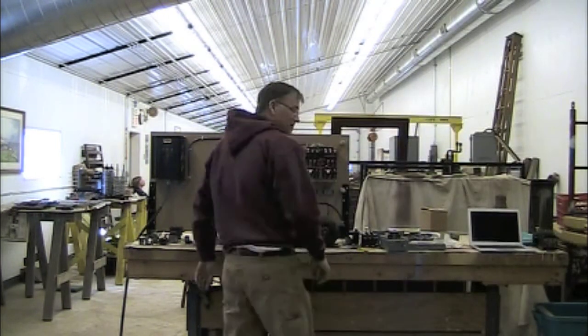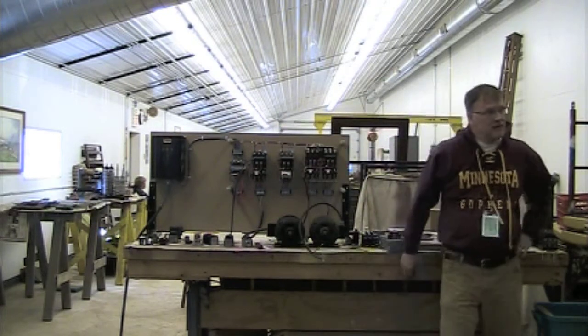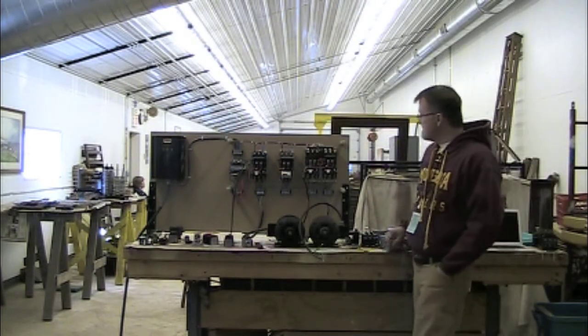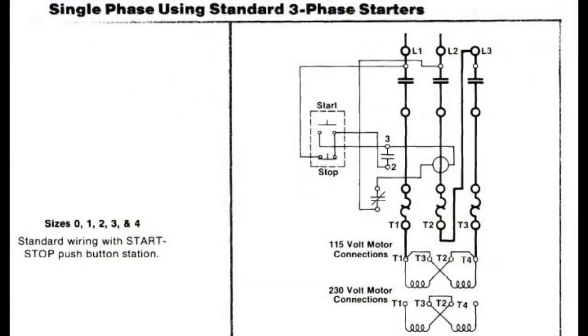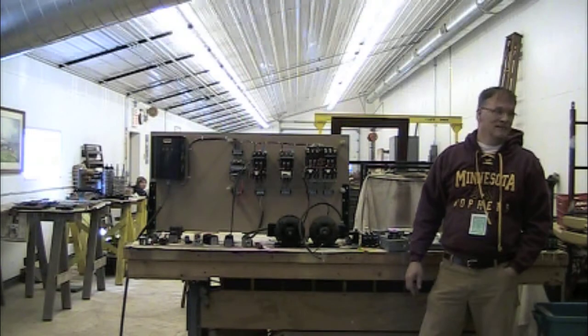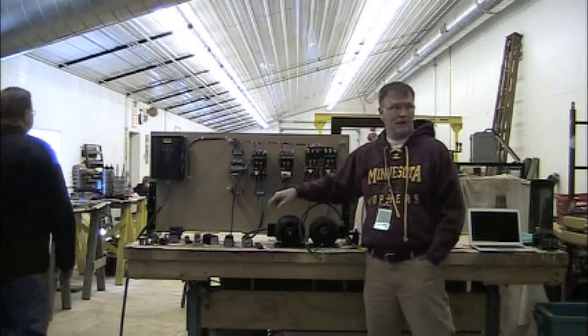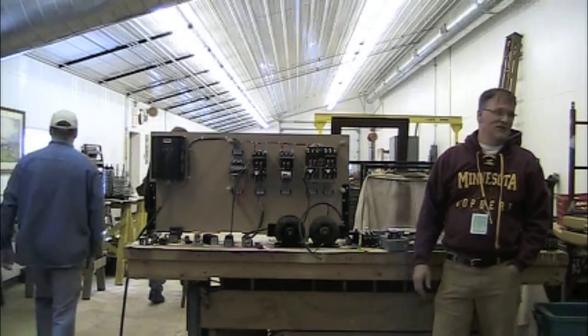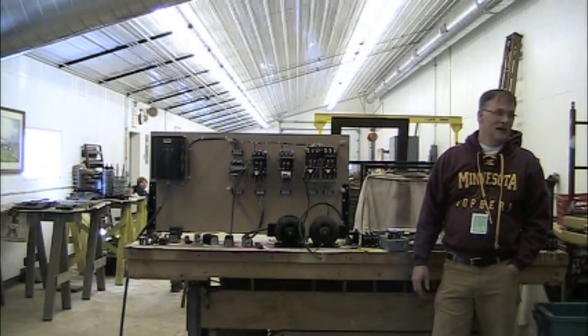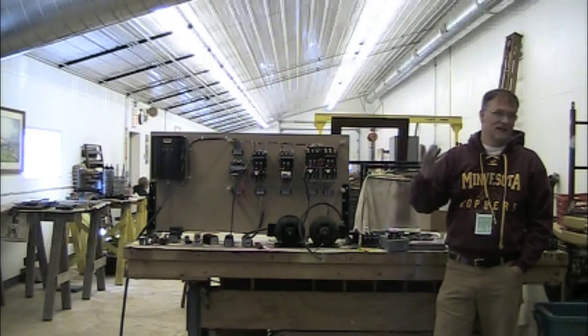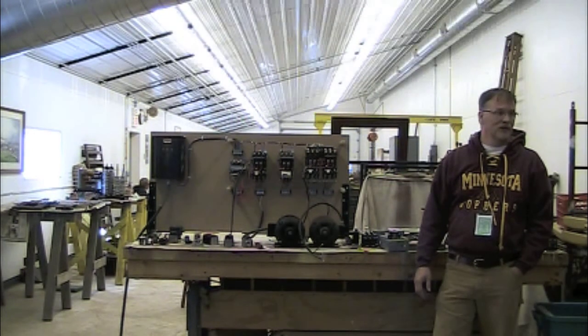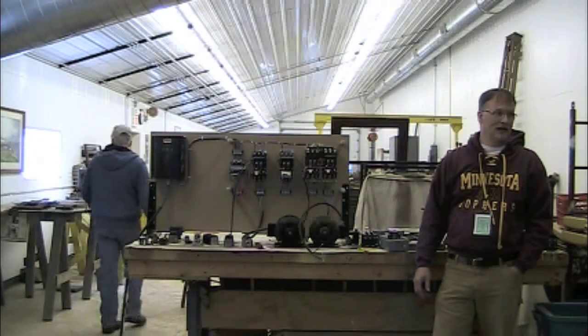You spoke about wiring these for single phase and having to have the power to both heaters. How do you do that in a three-phase contactor with both coupled like this? If you have single phase coming in and you're just coming into 2 legs, one wire comes through, the overload down here goes back up to the top and goes through. So it's just the same current going through all 3 of them. Run it back through the contactor as well as the heater wire. Yeah, one wire off of here goes up to the top and comes through. Not all manufacturers design them that way, but that's specific to the Allen Bradley side because that's the way their values are tuned, specifically for what you look up in that chart, so that all spots are occupied.